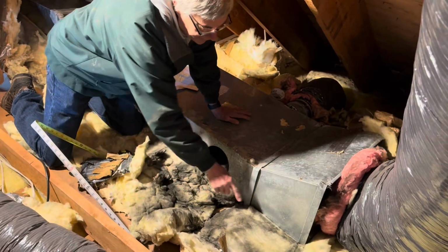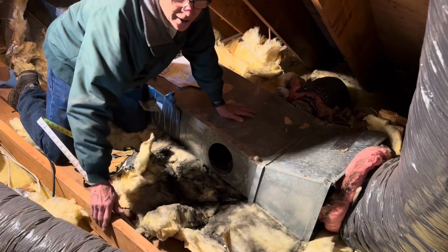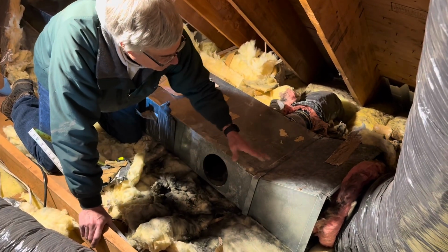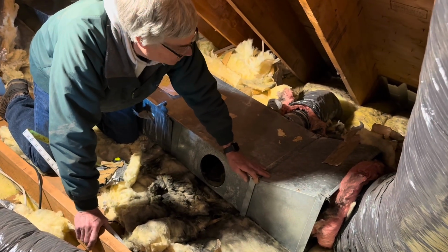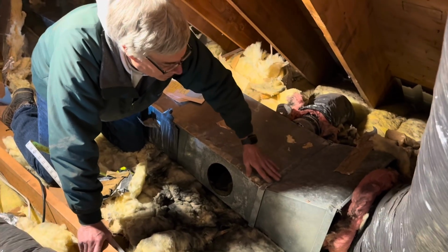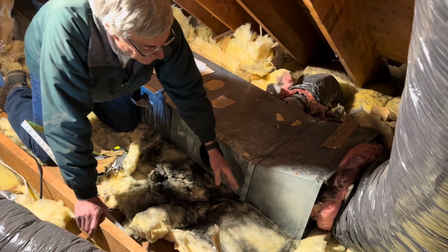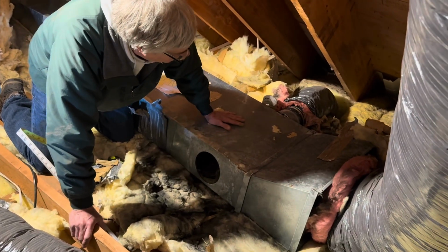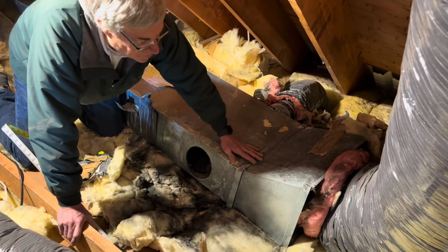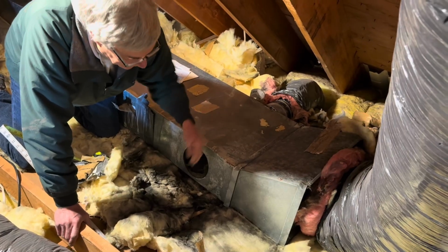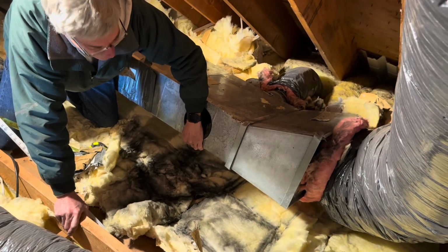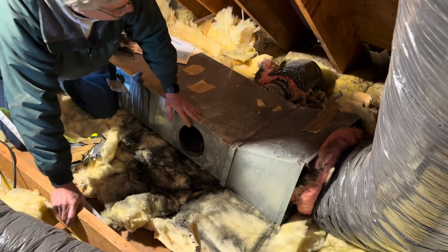So we know that it leaks just about everywhere that there's air flowing through it, and that's going to be this connection, this connection. These connections we're going to have to seal, and we're going to seal them with a mastic. And that mastic needs to be thoroughly applied to fill in all the holes and gaps to eliminate all the leakage. It's a little bit harder when we have an existing system, because we have to lift it up and get underneath, because it's leaking on the bottom as well. And if you pick it up, you see where all the leakage is because there are all the black lines. So we have to solve that.